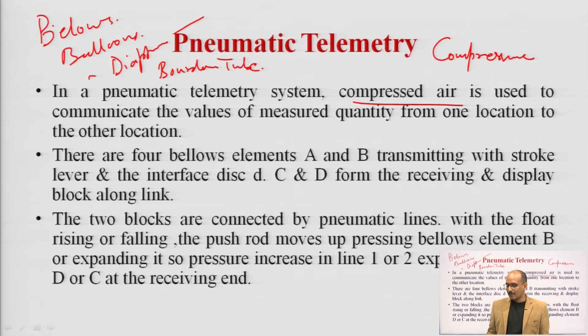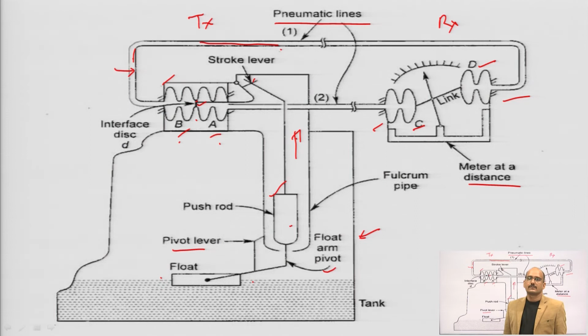More specifically, you can understand this point directly: there are 4 bellows elements, A and B for transmitting with the stroke levers and the interface disc, and C and D for the receiving and display block along with links. The 2 blocks are connected by pneumatic lines. With the float rising or falling, the push rod moves up, pressing bellows element B or expanding it. So, increased pressure in line 1 or 2 will expand element D or C at the receiving end. This particular cylindrical tube is known as the fulcrum pipe.